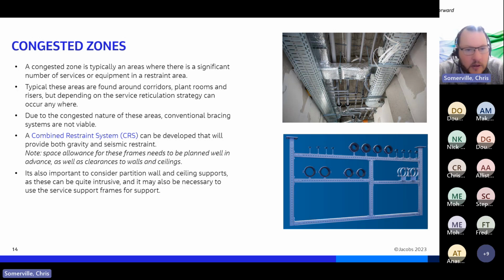The key one as well is looking at the clearances. I've gone into projects where we've got all the services going down the corridors completely packed, but there's no allowance for frames. Some of these frames can be 100 mil, and then you need 50 mil clearance from the sides, so you're almost talking 150 mil either side, 300 mil off your corridor. If you've got a corridor that's only 1500 wide, straight away you're losing a good portion of that just to allow for clearances and framing.